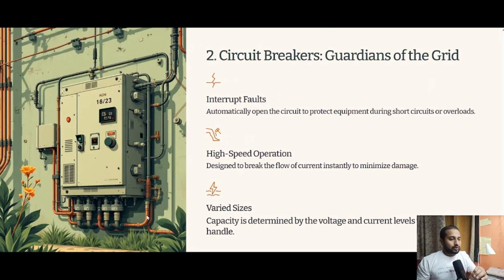Then next important equipment is circuit breaker. They are the guardians of the grid. They interrupt the fault and automatically open the circuit to protect equipment during short circuits or overload. Then they have high speed operation. They are designed to break the flow of current instantly to minimize the damage.